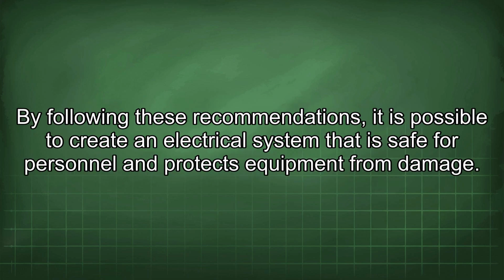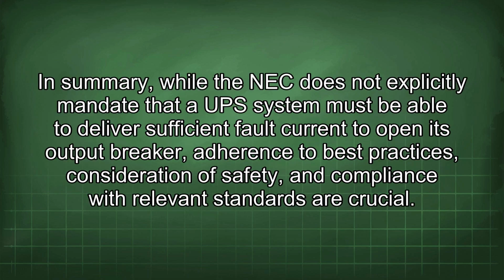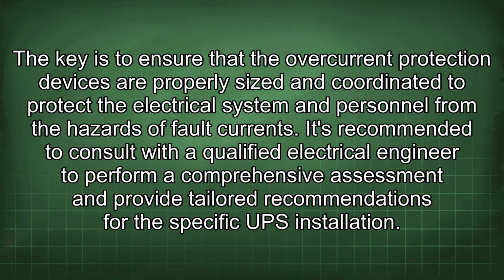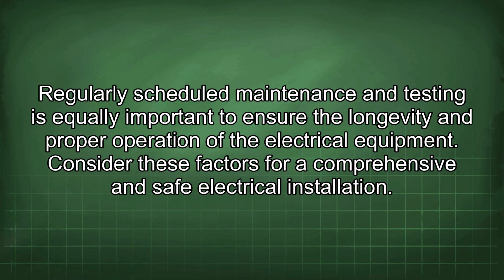By following these recommendations, it is possible to create an electrical system that is safe for personnel and protects equipment from damage. In summary, while the NEC does not explicitly mandate that a UPS system must be able to deliver sufficient fault current to open its output breaker, adherence to best practices, consideration of safety, and compliance with relevant standards are crucial. The key is to ensure that the overcurrent protection devices are properly sized and coordinated to protect the electrical system and personnel from the hazards of fault currents. It's recommended to consult with a qualified electrical engineer to perform a comprehensive assessment and provide tailored recommendations for the specific UPS installation. Regularly scheduled maintenance and testing is equally important to ensure the longevity and proper operation of the electrical equipment. Consider these factors for a comprehensive and safe electrical installation.